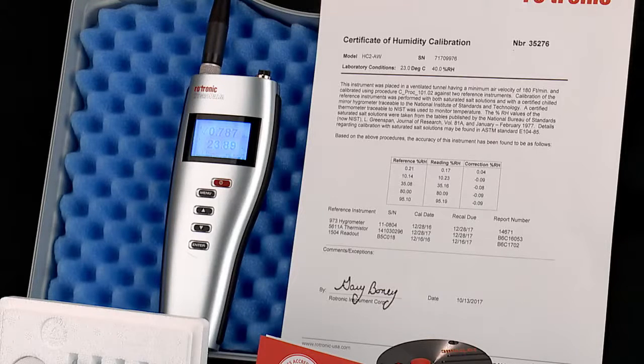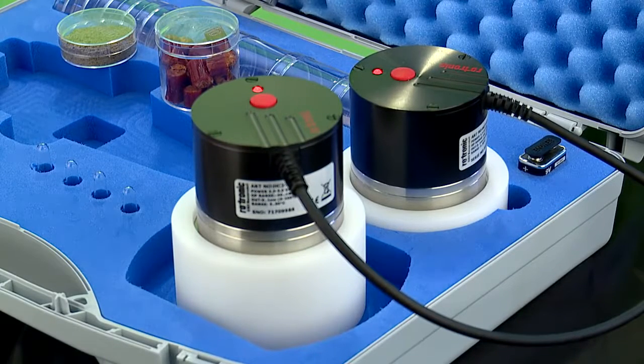The second important concept for the calibration of the Rotronic AW probes are the steps taken to perform the calibration. Unlike many measurement instruments where the calibration and adjustment of the measurement point is performed at the same time, Rotronic has separated this one step into 2 steps. This is for increased accuracy and for a true as-found reading. So, the first step is to collect all of the as-found calibration points and save each test point. The second step would be to apply the calibration points if desired. As with sample preparation, it is important that the instrument and the standards are at the same temperature. Nothing crazy here. A normal office or lab environment is fine. Just avoid direct sunlight and ventilation vents.